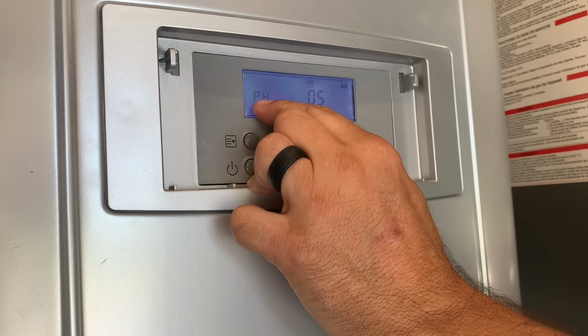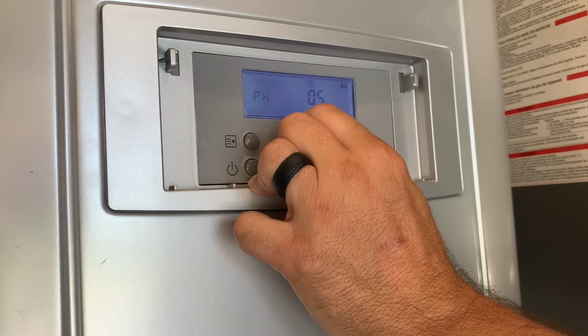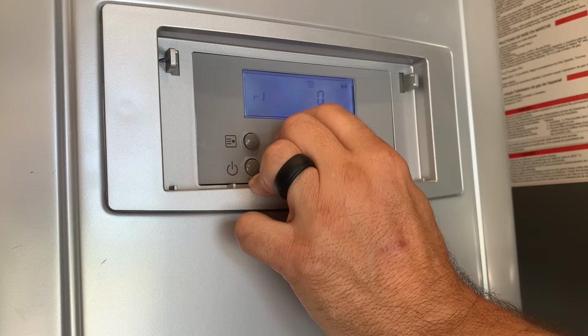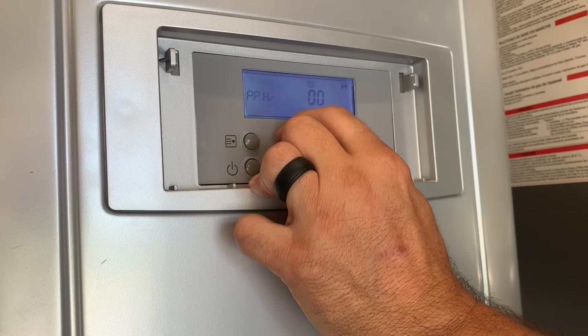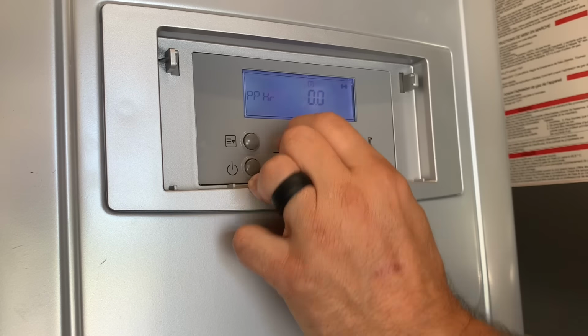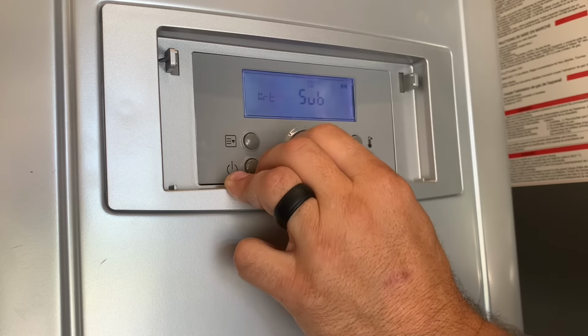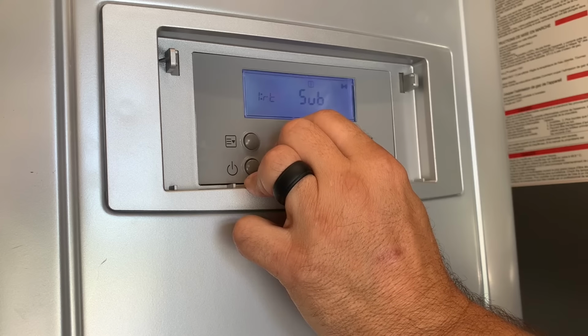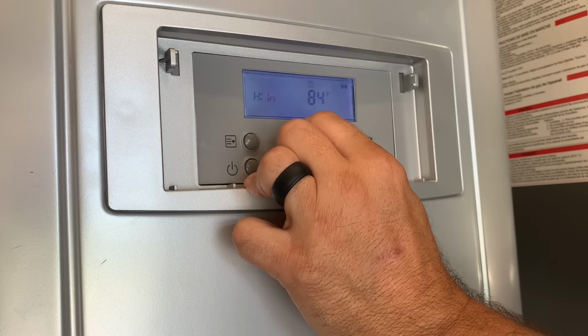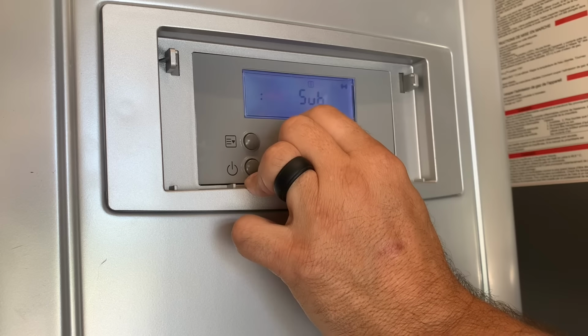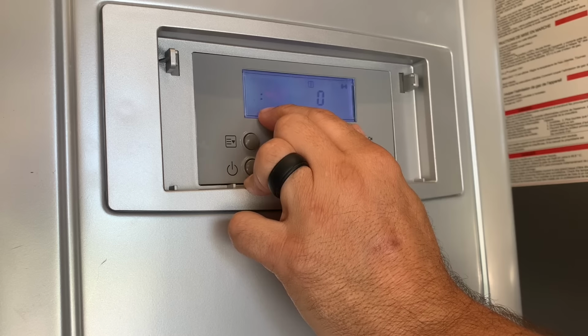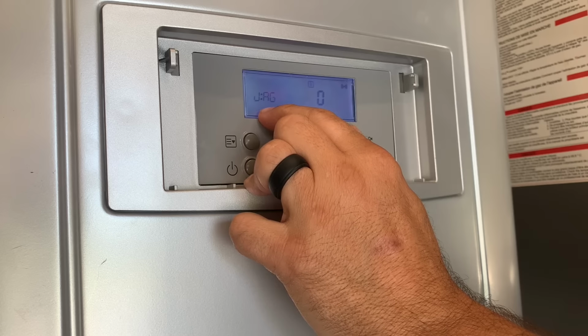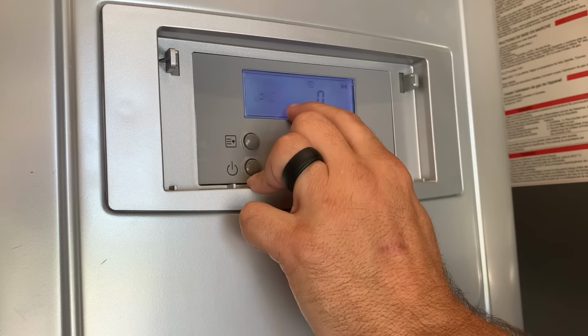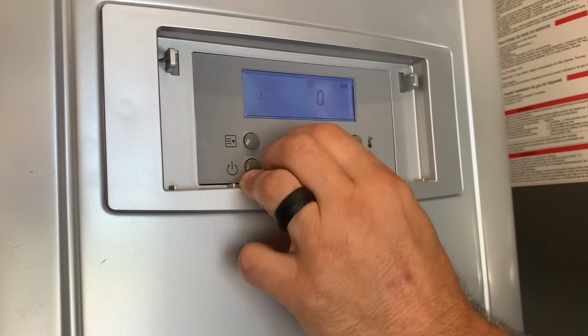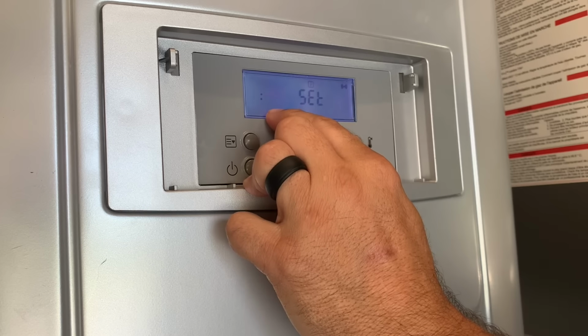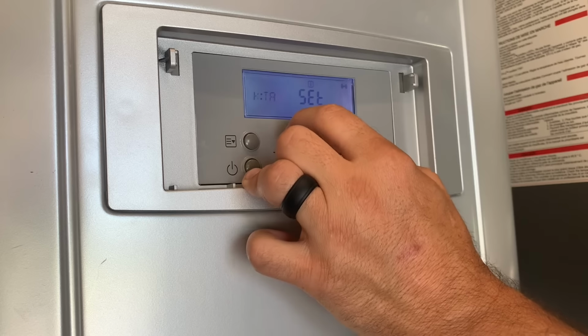So to access those again, here's PH for power on time, RH, burner operating time, BNCY, burner cycles, PPHR, pump running time. Now we can just back out of that. Go back to the IRT, and remember that's just one down from the water inlet temperature. It's got its own submenu. JAG, adjusts AGM position. Ranges from positive or negative 50, just defaults to 0 here. And remember KTA for selecting your date and time is last on the menu.